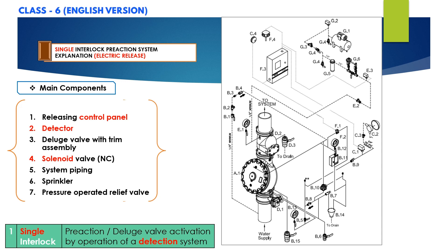Let's discuss the system operation in detail using a schematic diagram. In the set condition, the system water supply pressure enters the priming chamber of the deluge valve through a 1/4-inch line, which includes a normally open priming valve, strainer, restricted orifice, and a check valve. This line is also connected to the normally closed solenoid valve and to the emergency release button. Water supply pressure is trapped in the priming chamber by the check valve and normally closed solenoid valve, and the pressure in the priming chamber holds the deluge valve clapper closed, keeping the outlet chamber and system pipe dry.